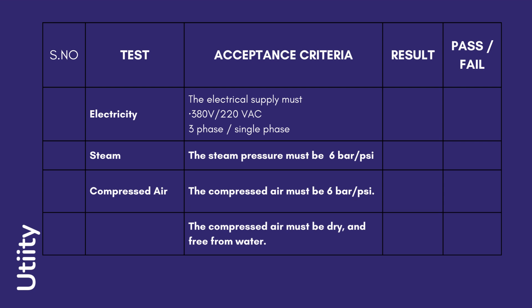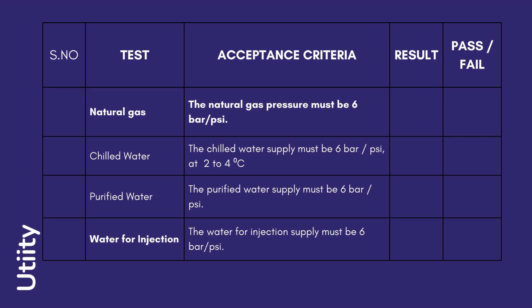Additionally, the compressed air must be dry and free from water or moisture. Natural gas — the natural gas pressure must be 6 bar or psi. Chilled water — the chilled water supply must be 6 bar or psi at 2 to 4 degrees centigrade. Purified water — the purified water supply must be 6 bar or psi. Water for injection — the water for injection supply must be 6 bar or psi.